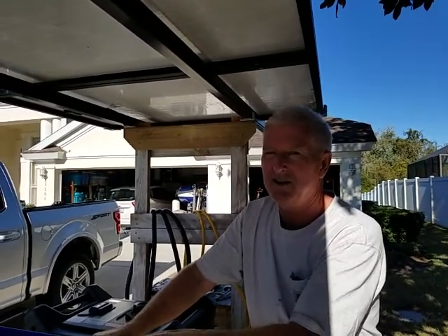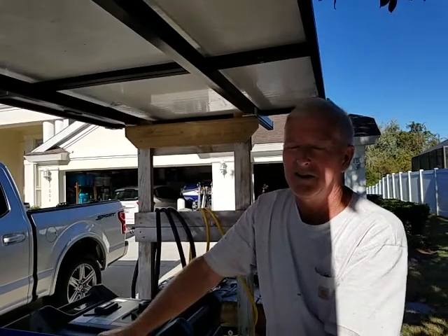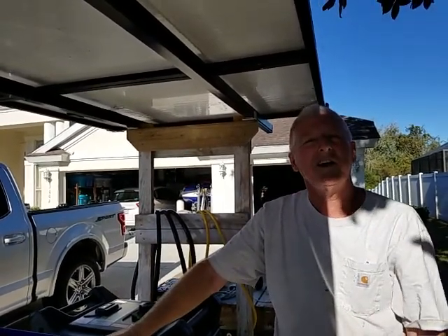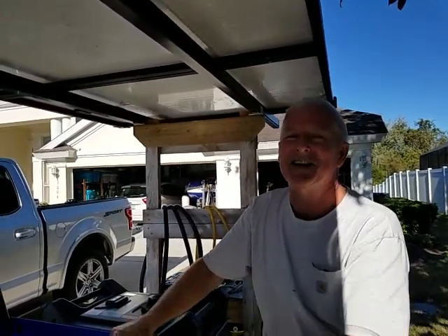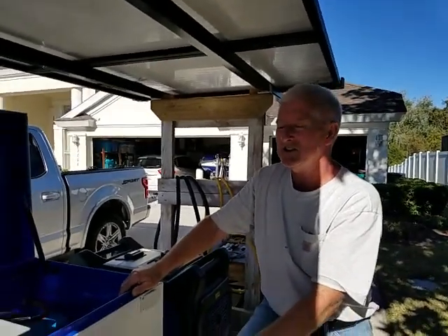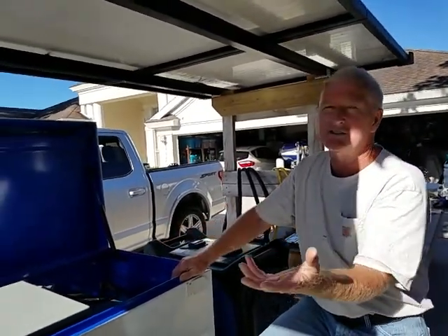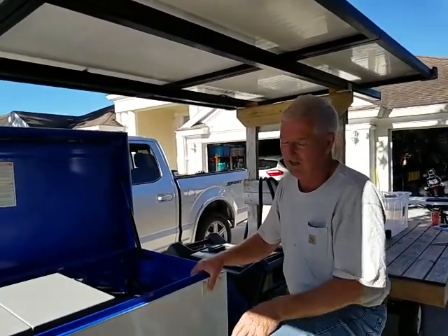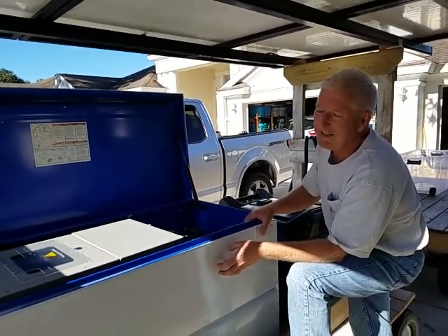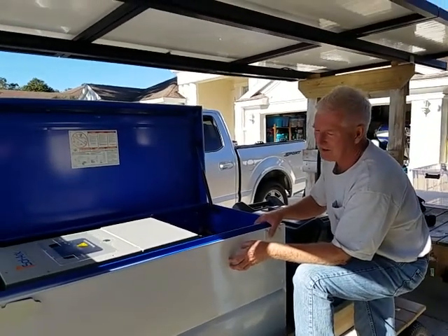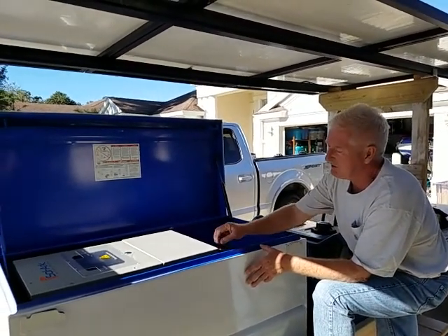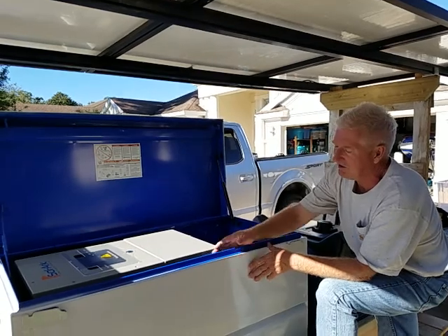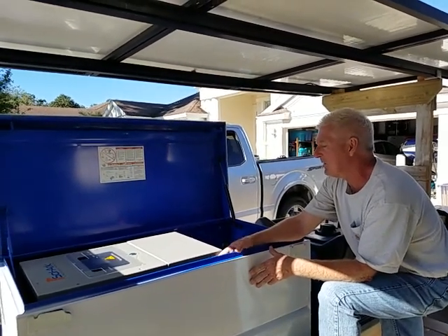Right. So what do we do for moisture control? Well, we don't care, because everything in this is outdoor rated. So you could literally set these outside. The box is more for security and physical protection. We may need to ventilate these. Sol-Ark wants a minimum of 6 inches between this edge and this edge. Okay, they want 6 inches of clearance. We're a little bit shy.